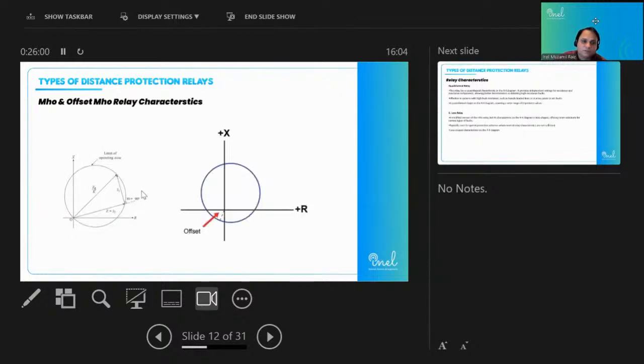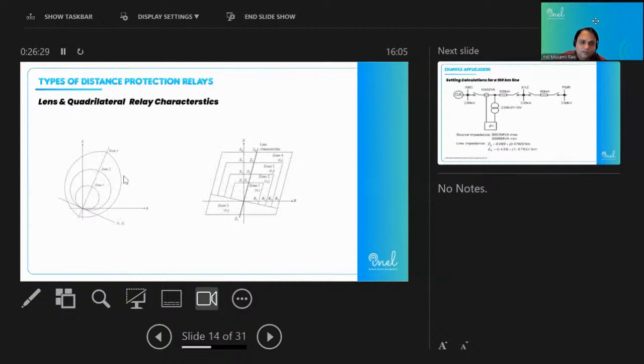Let me show you that one. If due to heavy loading the impedance of the line comes at this location, then this Mho relay will get operated. But now we are taking this portion out and making the impedance of the line during operation come at this location, then there will be no maloperation of the relay. So this is the lens characteristic, which is used for those lines which have high power flow and are heavily loaded.